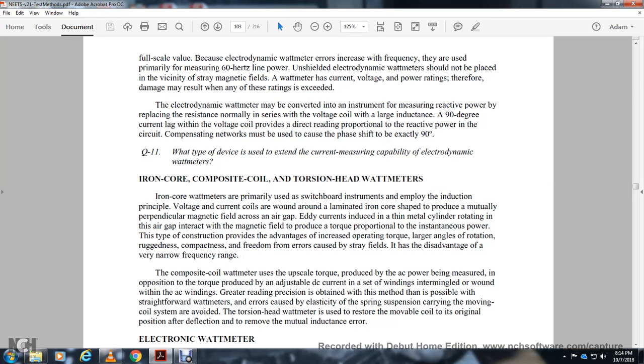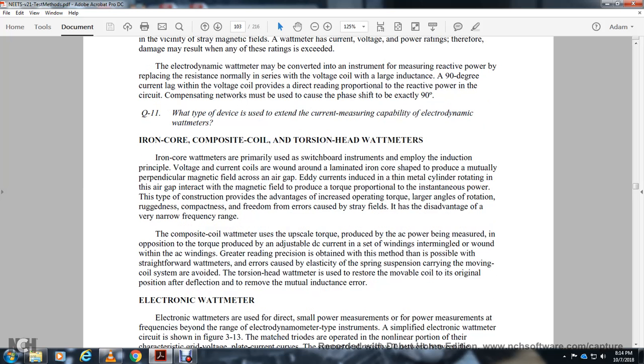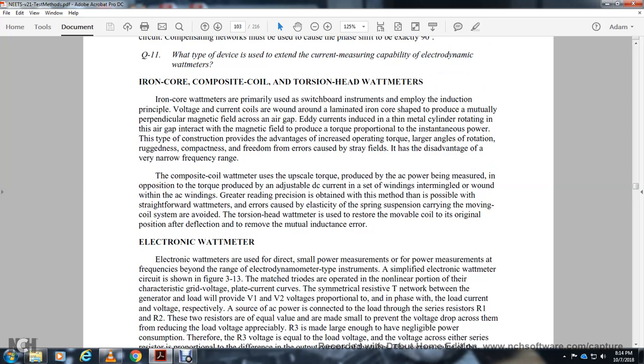Iron core watt meters are primarily used as switchboard instruments using the induction principle. Voltage and current coils wound around an iron core produce eddy currents in a thin metal cylinder rotating in an air gap, which interact with the magnetic field to produce torque proportional to instantaneous power. This construction provides large angle of rotation, ruggedness, compactness, and freedom from stray fields. The upscale torque is provided by the AC power being measured, with the opposing torque produced by adjustable DC currents. A torsion head is used to restore the movable coil to its original position after deflection.